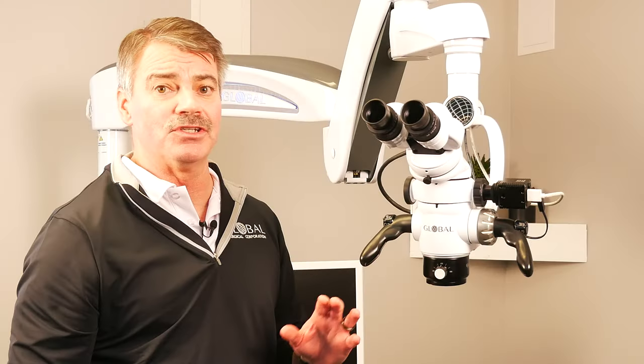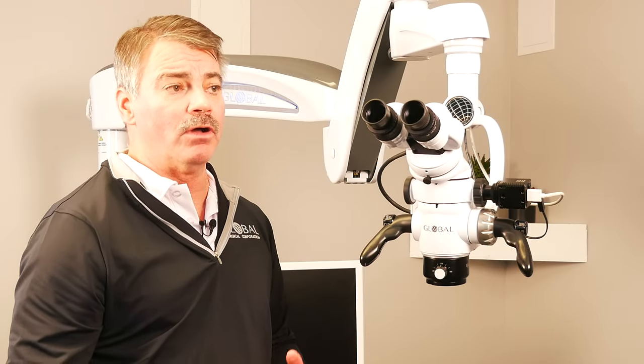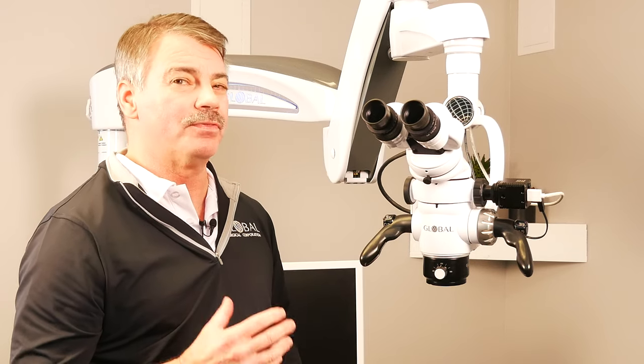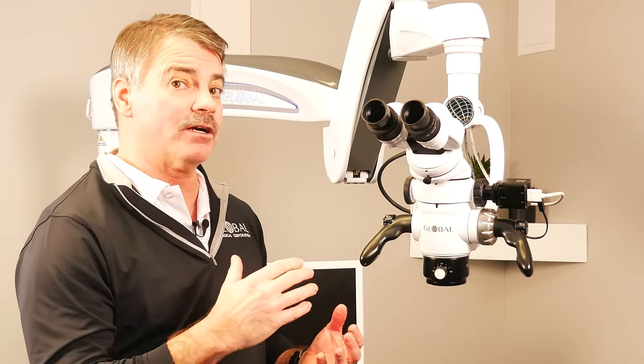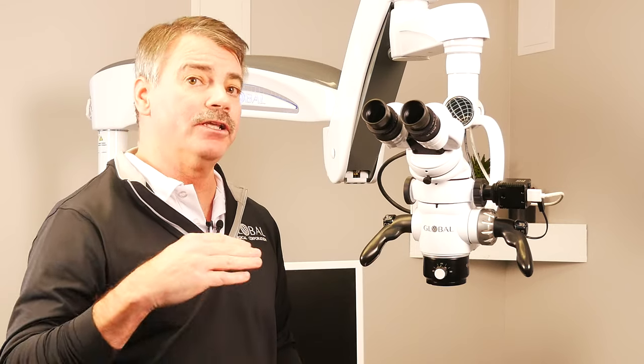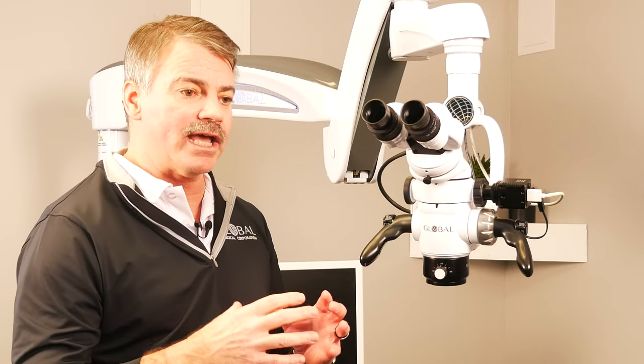The Global Microscope uses 10x eyepieces, while others in the industry use a 12.5x eyepiece. What that does is increase the bottom magnification available on the microscope. So instead of starting at, say, that 2.1x that the Global does, they'll start at nearly 4x, so they lose that super wide field of view that many operators like to have, particularly when they're just starting to use the microscope.